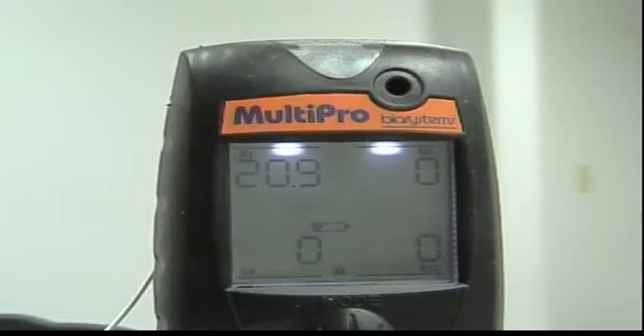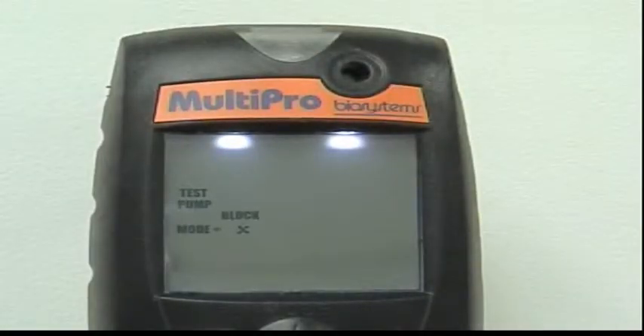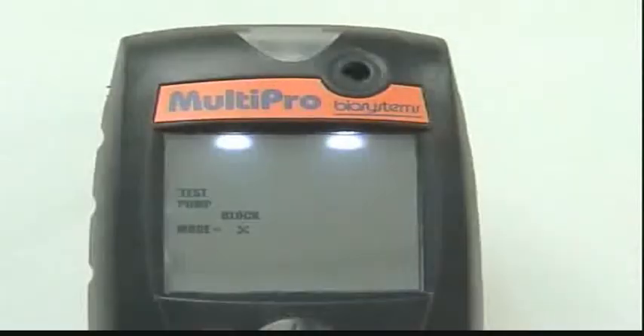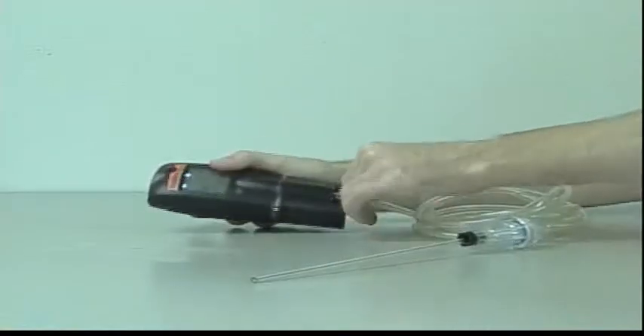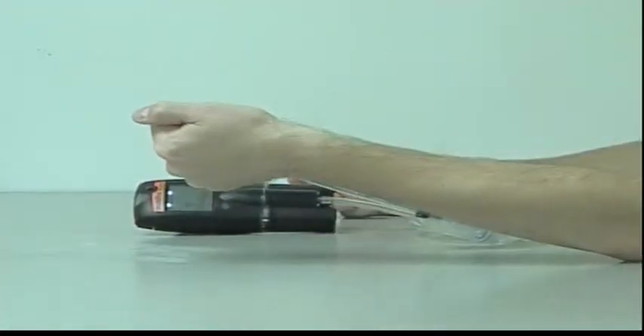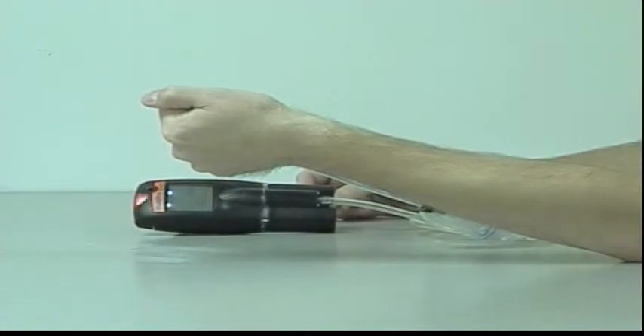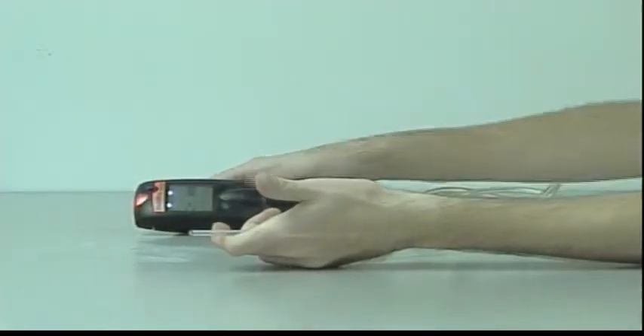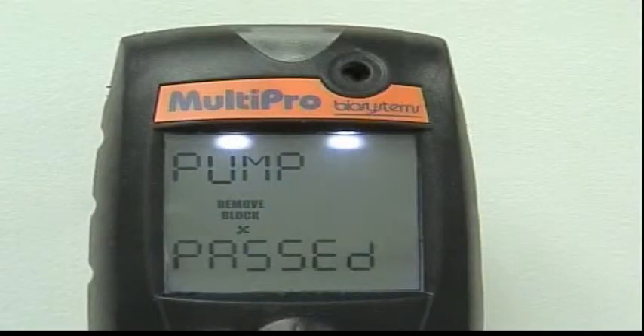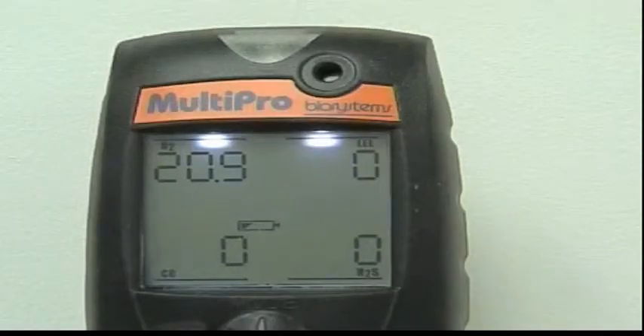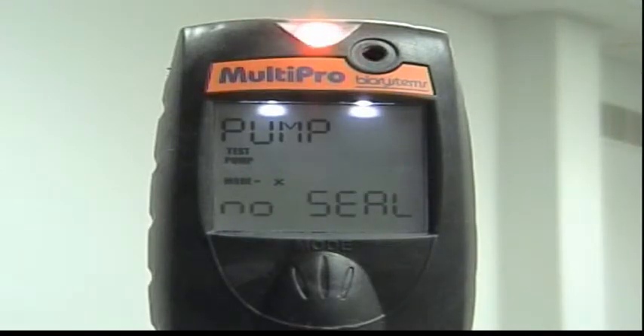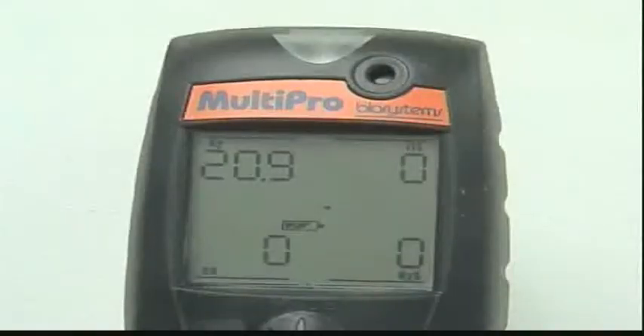If the pump is attached to the MultiPro when the instrument is turned on, the pump will be activated and the sample draw assembly will be tested for leakage. The MultiPro will instruct you to block the sample draw probe, which must be attached to the inlet port on the pump during use. Block the pump inlet by placing a finger over the end of the sample probe assembly. Once the instrument recognizes that the sample has been blocked, it will instruct you to remove the blockage. Once the blockage is removed, the instrument will proceed to the current gas reading screen. If the MultiPro is unable to detect a proper seal between the instrument and the pump, the display will instruct you to remove the pump. Once the startup sequence is completed, the current gas reading screen will be shown.